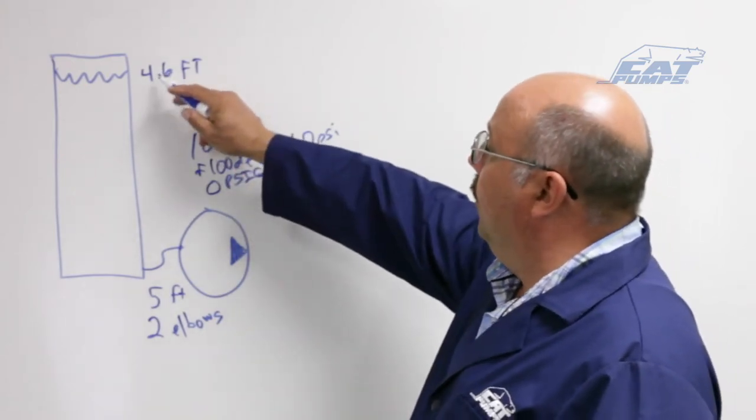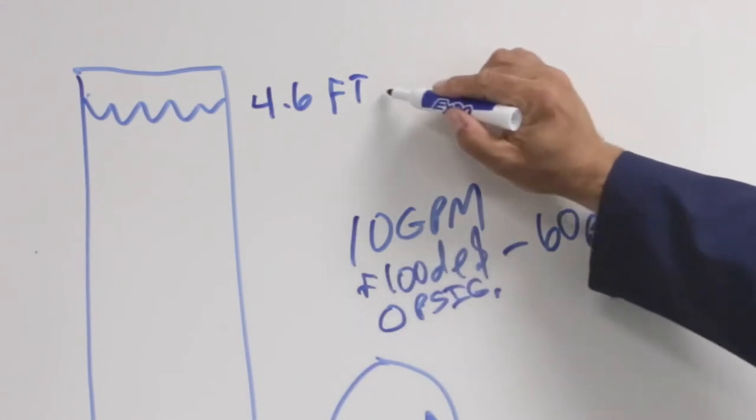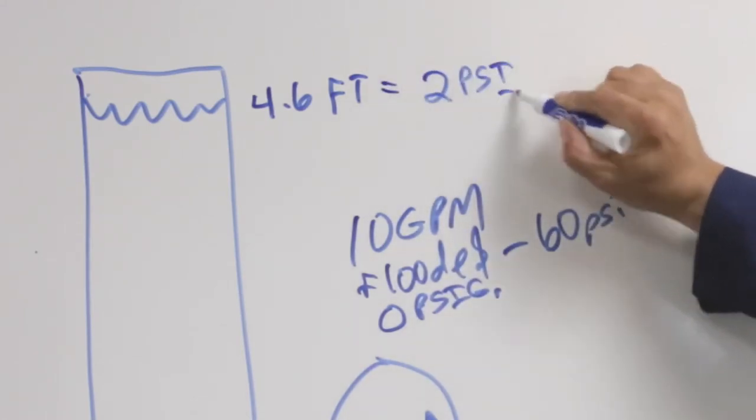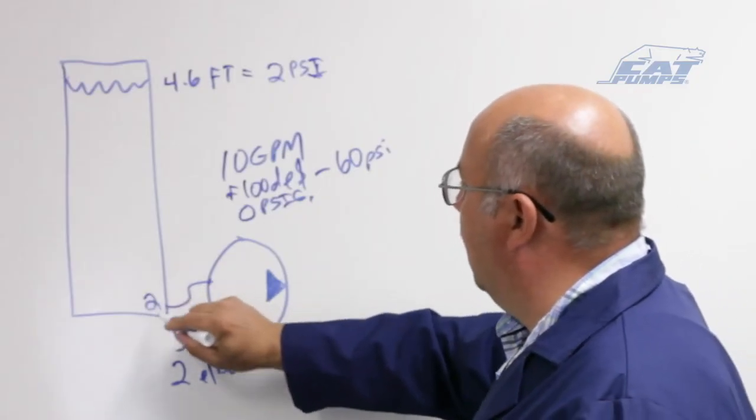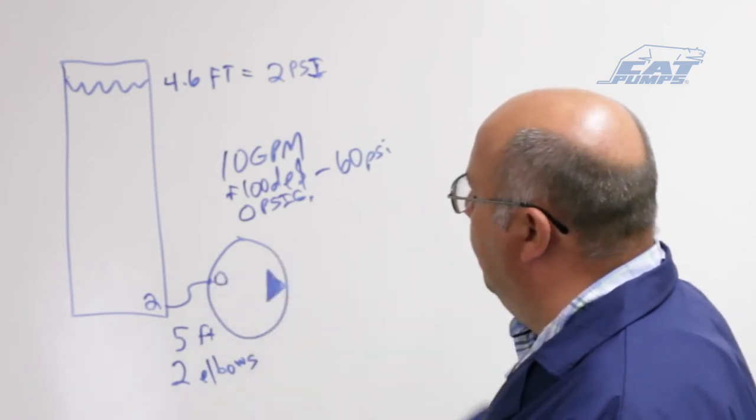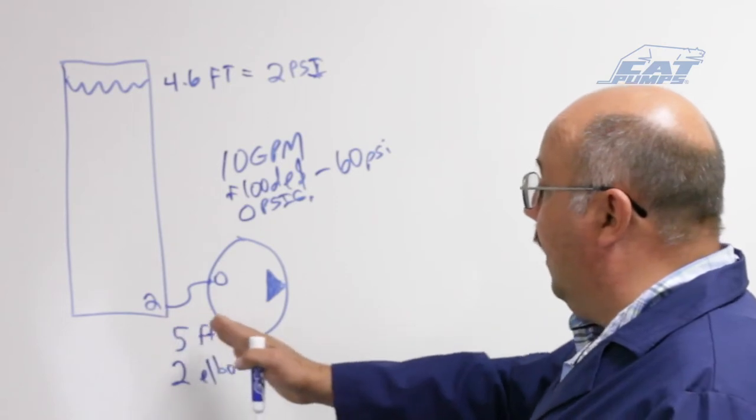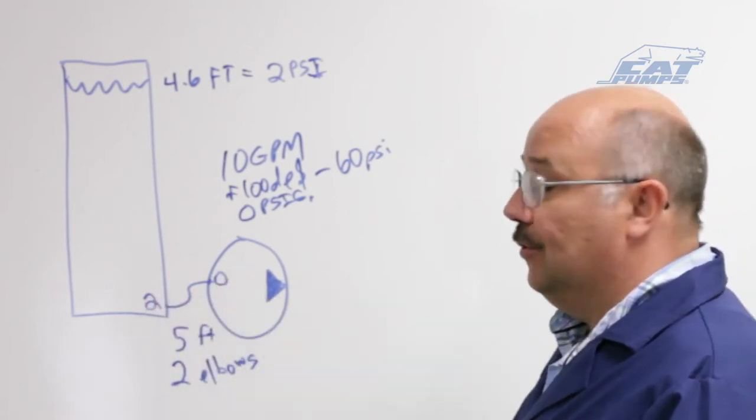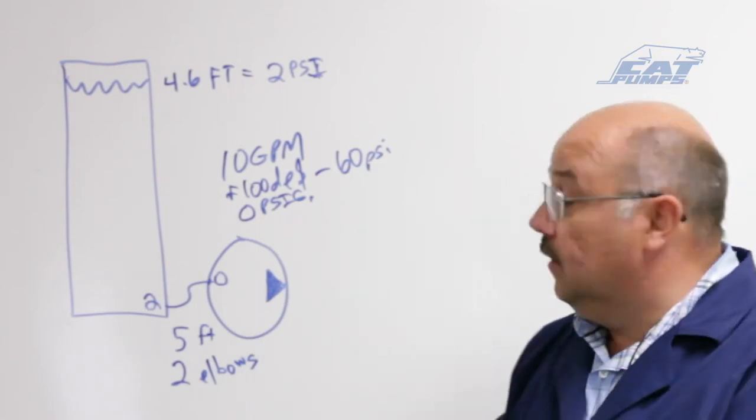Well, you might think we have 4.6 feet of water. That's a lot of water. But in reality, that equates to 2 PSI. So here at the bottom of the tank, we have 2 PSI. And the lowest we can go is zero. So we have to find a line size that's 5 feet long with 2 elbows that drops less than 2 PSI. So let's just start doing that calculation.